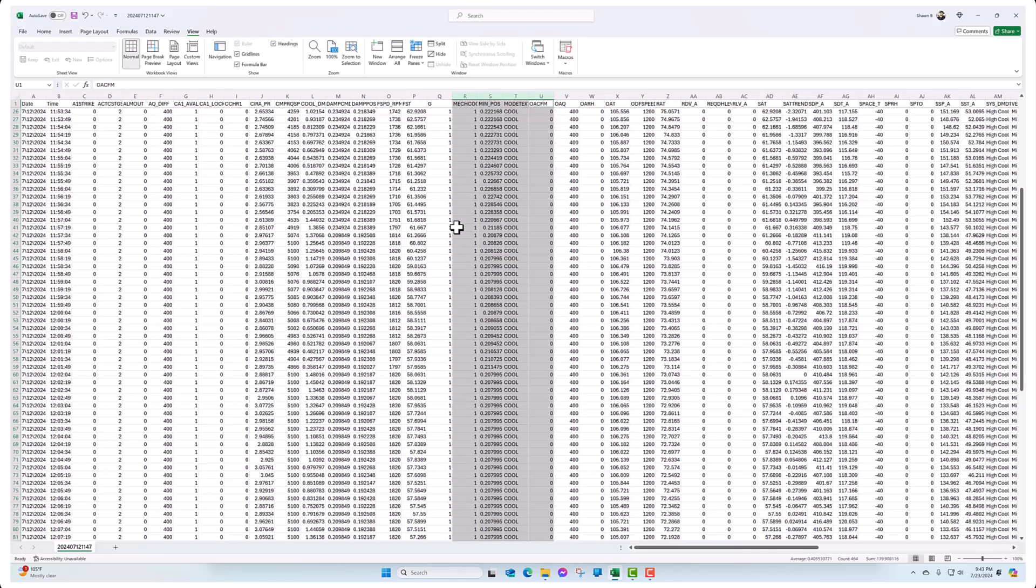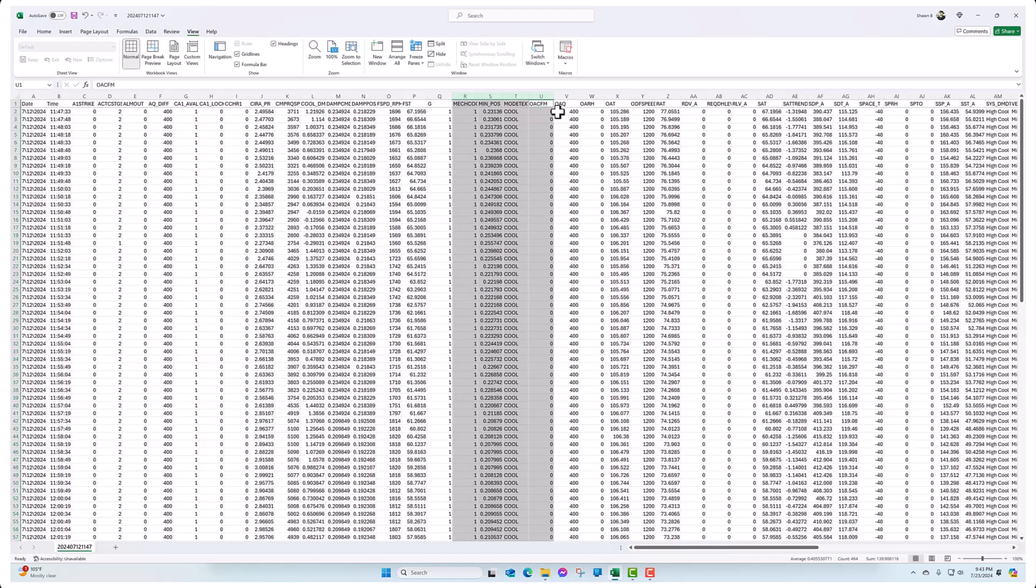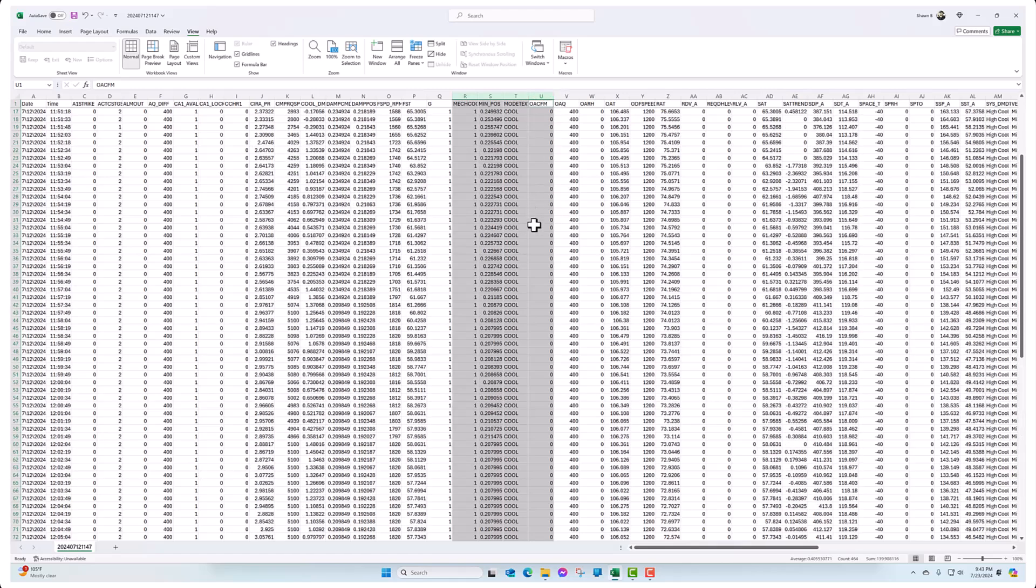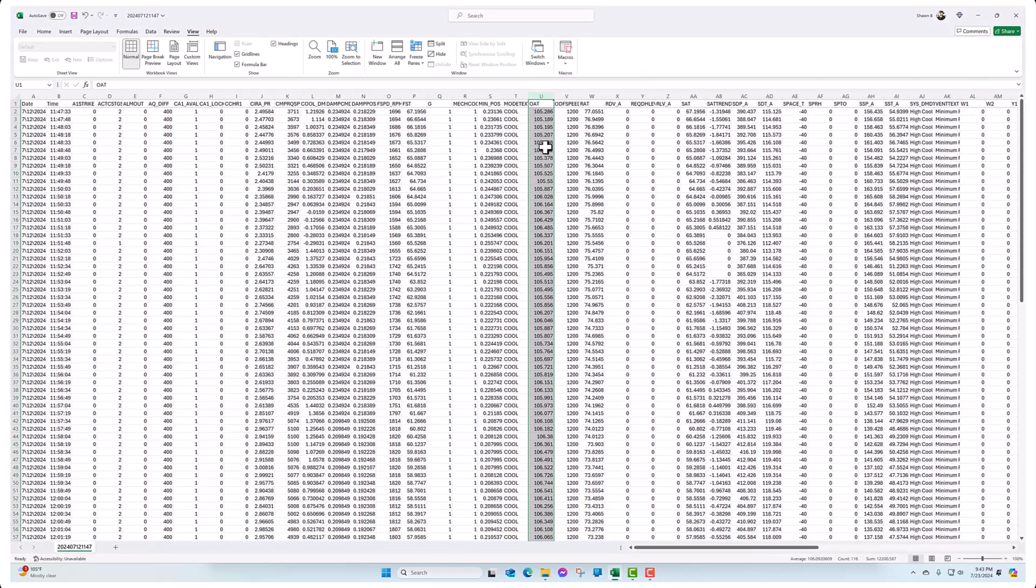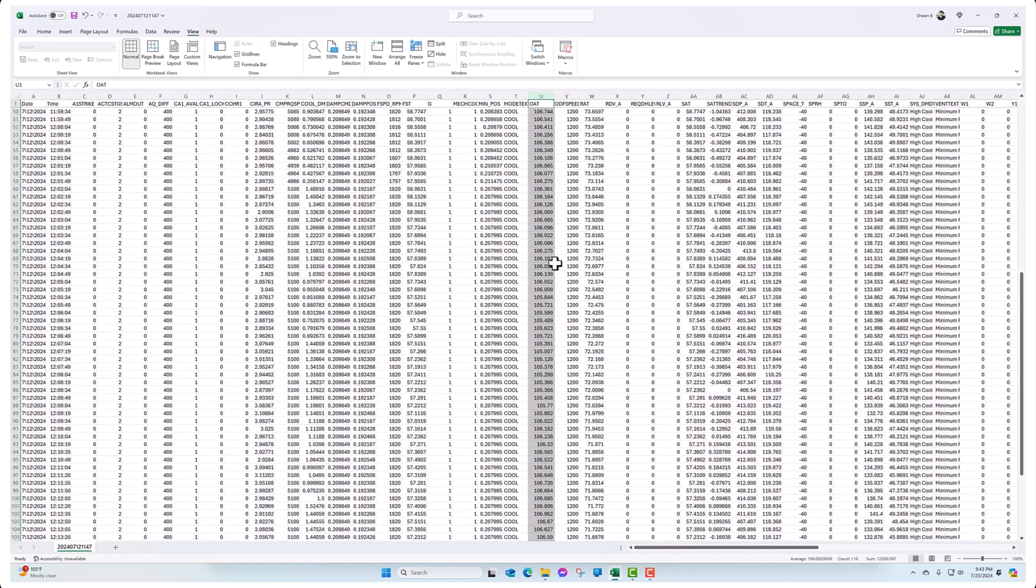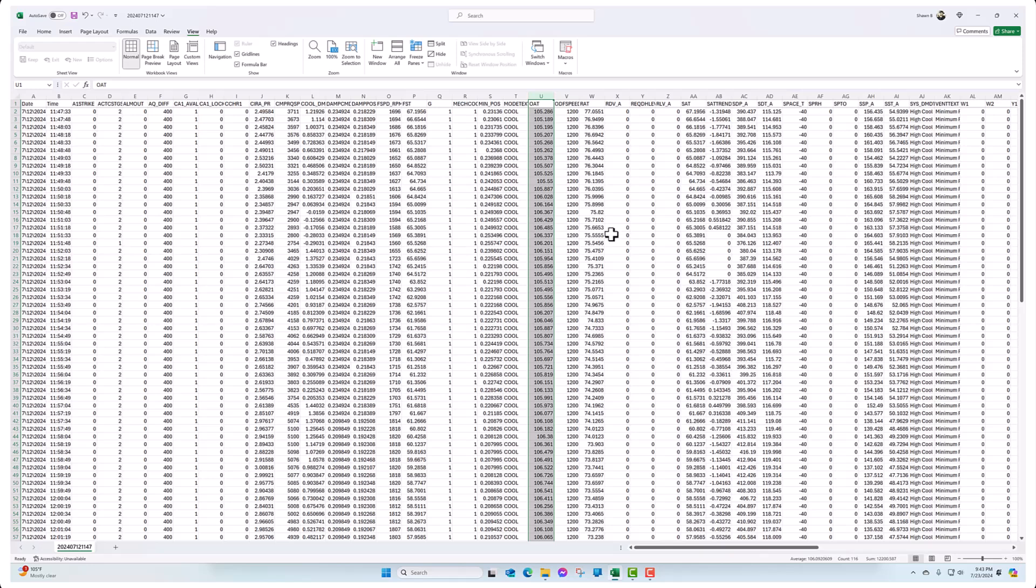There's a bunch of things I don't need. I'd have to look them up and see what they are. Mechanical cool. It's pretty much on the whole trend I have here. ACFM. I could just get rid of those. And when you set up the training, you kind of just setting up a bunch. Here's outside air. Humidity. We're not reading that. We're just reading the dry bulb temp. The sensor is your outdoor fan speed, which is just pegged to 1200. We have that juiced up a little bit. Factory was 1100, but it's really hot where this is like 115 degrees hot.